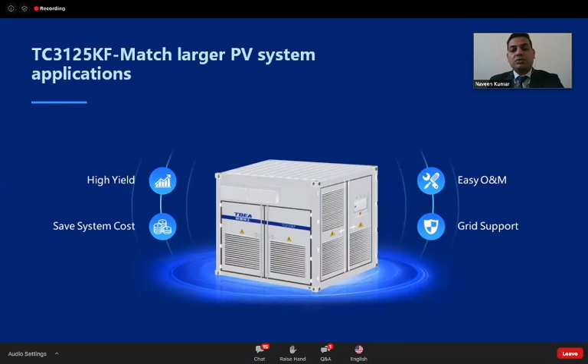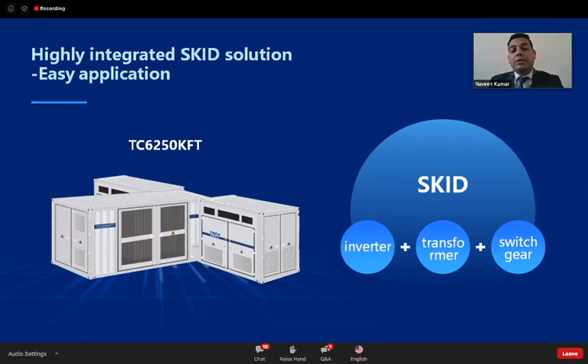Moving on to the skid solution. This 3.125 megawatt container can be used in skid solutions also. Skid solution means we are providing a complete ITS solution which includes inverter, transformer, and the MV switch. This can be used where project timelines are very tight and manpower is very difficult to get. So this kind of solution is a plug and play solution. It can reduce time and cost.